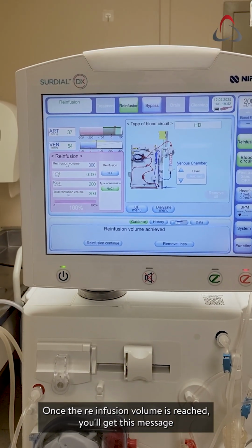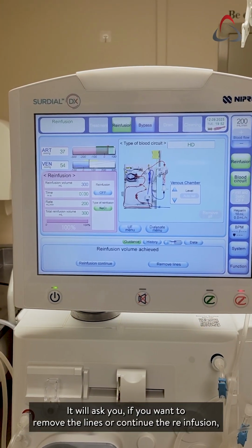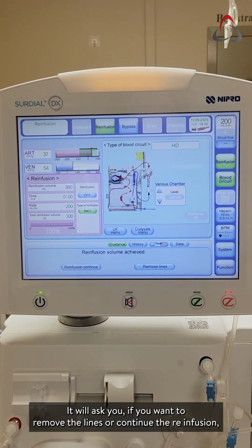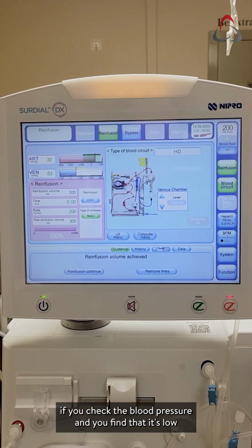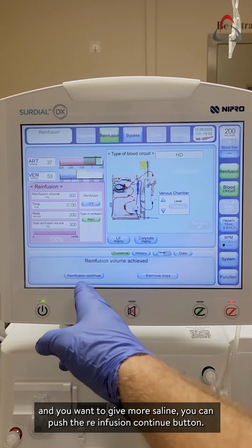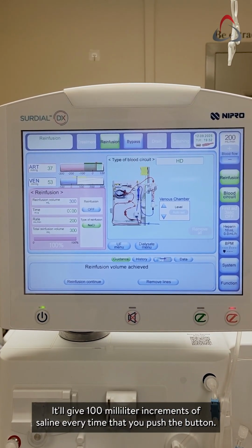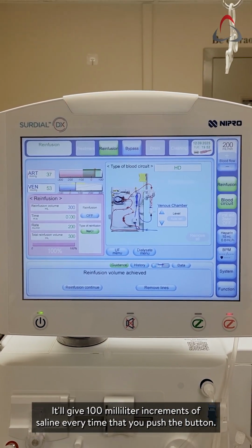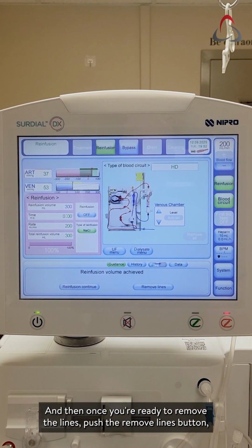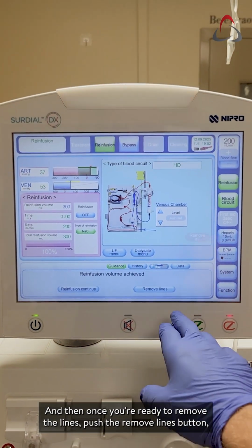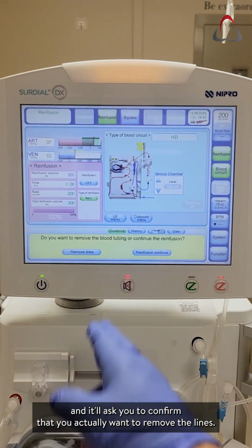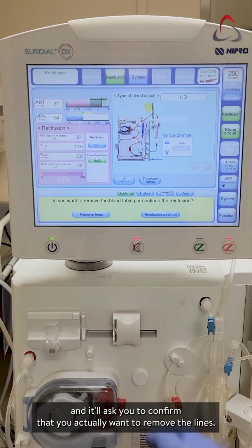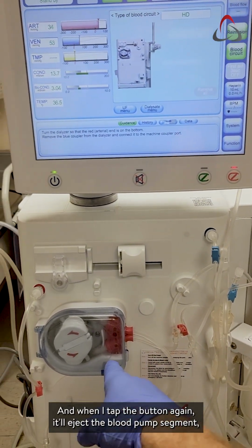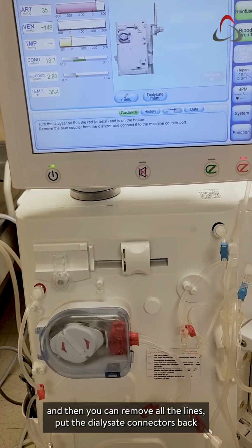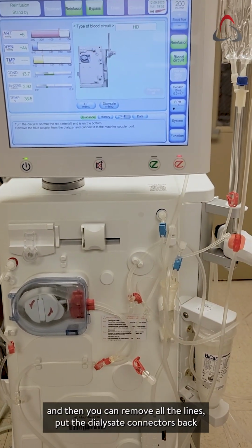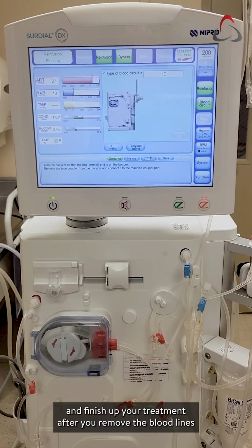Once the reinfusion volume is reached, you'll get this message, and it asks if you want to remove the lines or continue the reinfusion. If you check the blood pressure and find that it's low and you want to give more saline, you can push the reinfusion continue button. It gives 100 milliliter increments of saline every time you push the button. Once you're ready to remove the lines, push the remove lines button, and it asks you to confirm. When I tap the button again, it ejects the blood pump segment. Then you can remove all the lines, put the dialysate connectors back, and finish up your treatment.